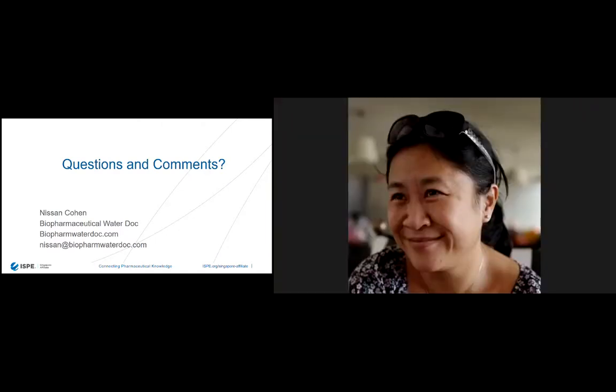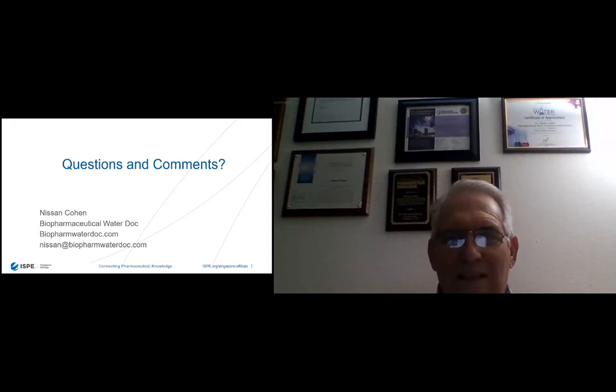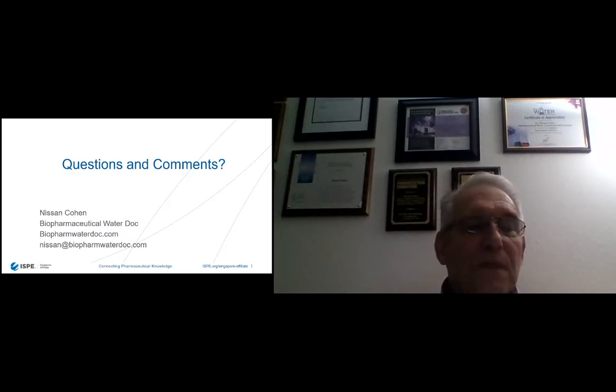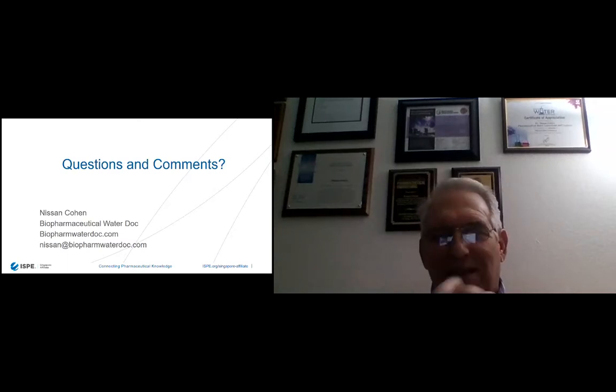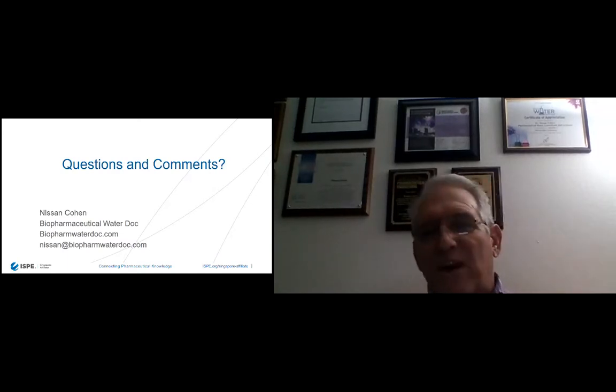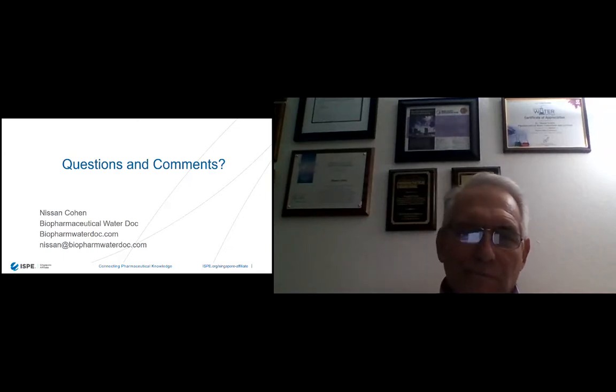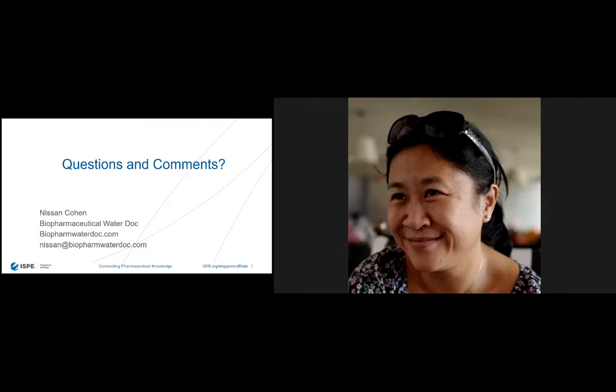Now, Dwys Molina asks, is there any effect of ozone, O3 sanitation, on the rouging process? The answer is nominal, because ozone runs at such a low level. Ozone normally runs only in ambient systems. It's best at 25 degrees Celsius. It can run as high as 35 degrees Celsius, fairly okay, but it's better in colder water, 25 degrees and less. The amount of ozone that is actually there is very, very small. So even though it's an oxidant and it can promote oxidation inside the system, it's very small in producing the amount of rouge. Okay, I hope that answered your question. If not, please send a follow-up question.